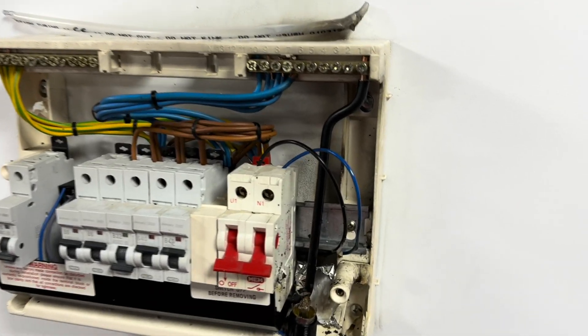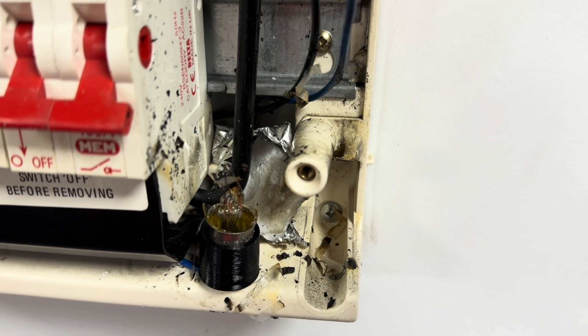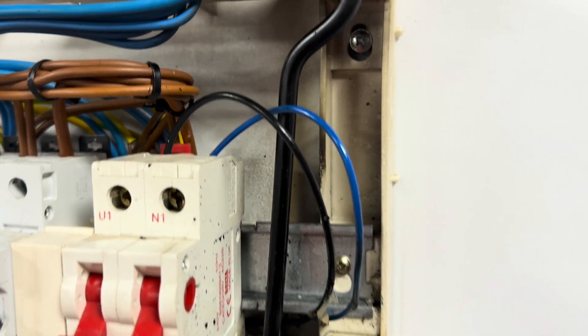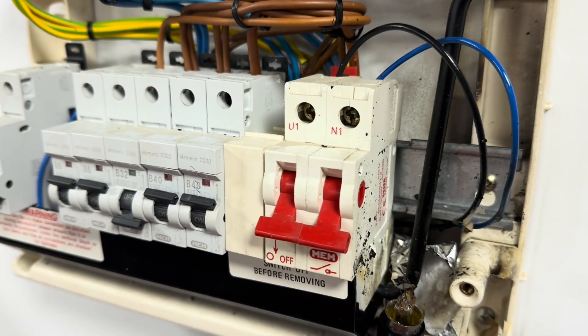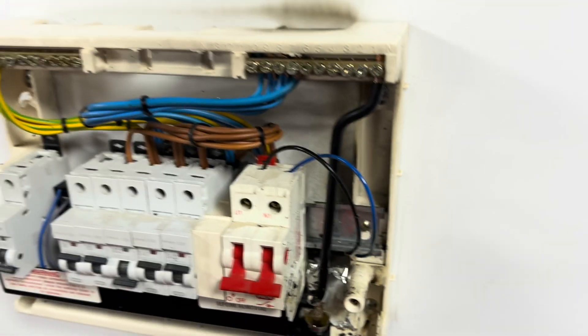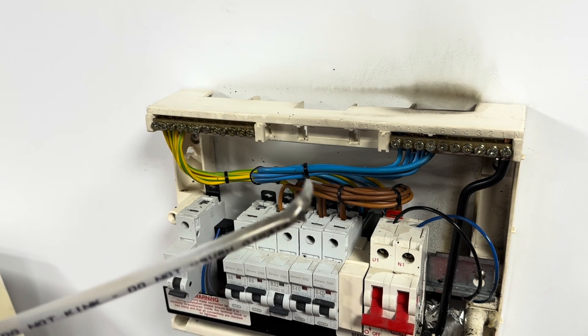I just thought I'd show you a close-up of what went on. You can see the fire lighter there, which was put out by the extinguishant, and it didn't relight — which was a good thing. There's some blackening up the back where there wasn't a good seal against the wall, but none of the cables are damaged and I think all the RCDs are actually probably still in working order. The tubing itself you can see just where it melted at the hottest point and discharged onto the fire.